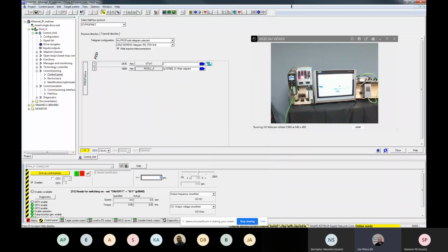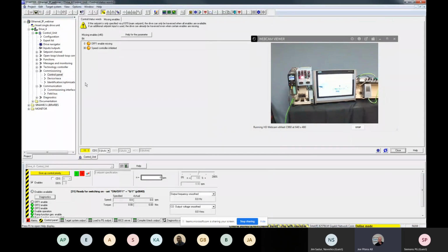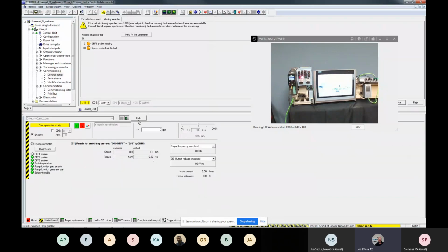Oh, by the way, if you don't see all of this additional information here, it could be because this button for additional diagnostics is not there. There is another button here for further diagnostics, which tells you which bits are missing. They'll give you the speed set point, the speed actual, the torque set point, torque actual, and we can see some predefined or selectable variables here as well. If you want to show this window bigger, drag it up to make the window bigger.